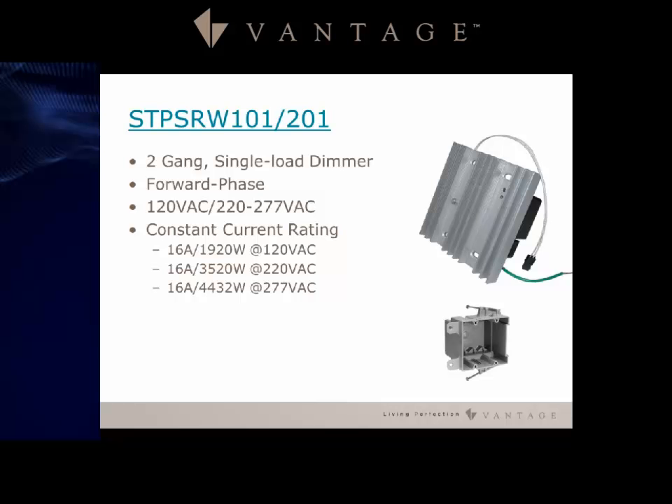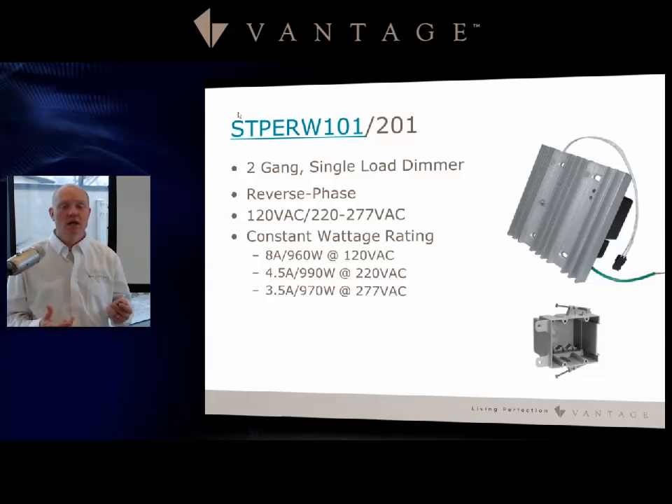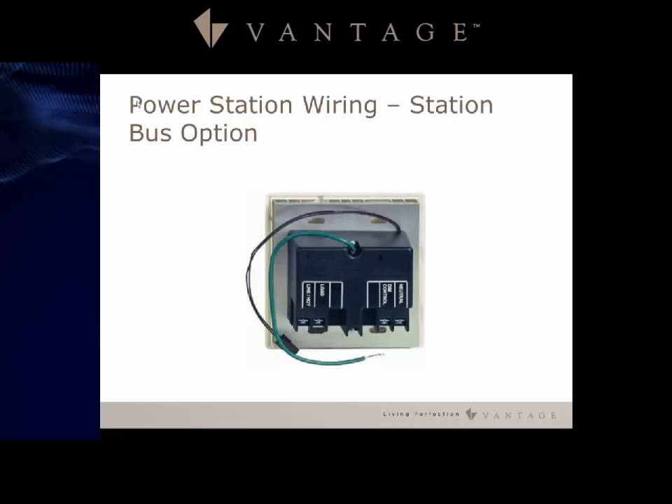For additional load control stations, the STP SRW 101 and 201 is a two-gang single load forward phase dimmer. The 101 handles 120 VAC and the 201 handles 220 to 277 volt applications. It handles a full 20 amp breaker derated to 16 amps. The STP ERW 101 is the reverse phase version for electronic loads, with a derating down to 8 amps depending on input voltage.